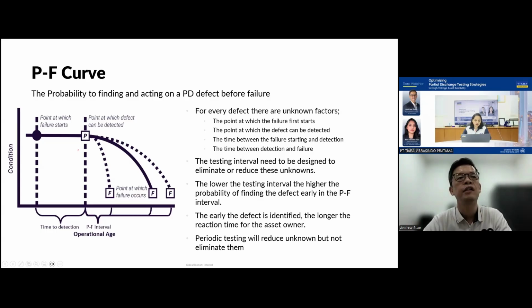This is the point at which the defect can be detected, but you may not be there to pick it up because you only go back every year, so you may waste some time. It depends on the type of failure. If it's a surface discharge, the time to failure can be very short, sometimes as short as a few weeks.